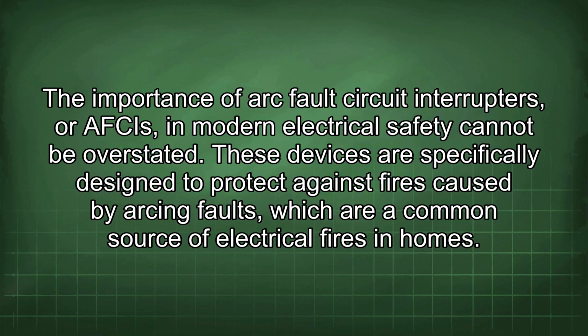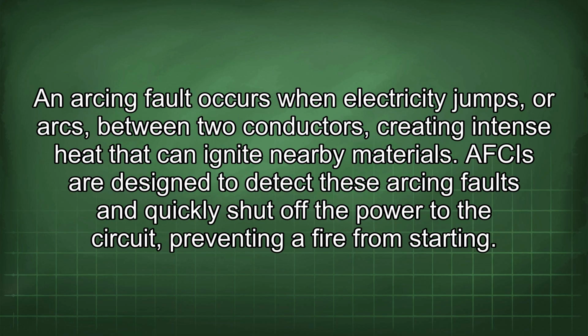These devices are specifically designed to protect against fires caused by arcing faults, which are a common source of electrical fires in homes. An arcing fault occurs when electricity jumps or arcs between two conductors, creating intense heat that can ignite nearby materials. AFCIs are designed to detect these arcing faults and quickly shut off the power to the circuit, preventing a fire from starting.